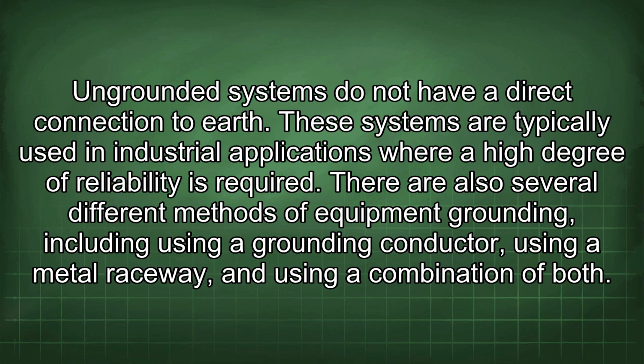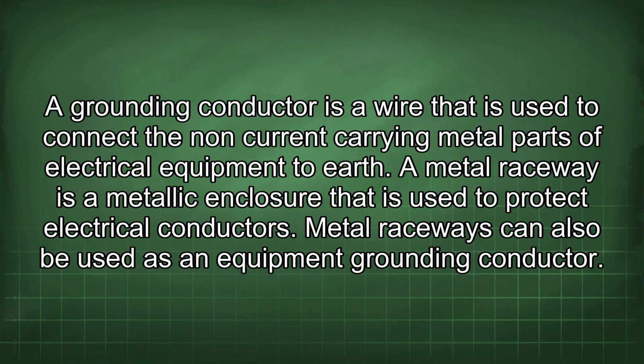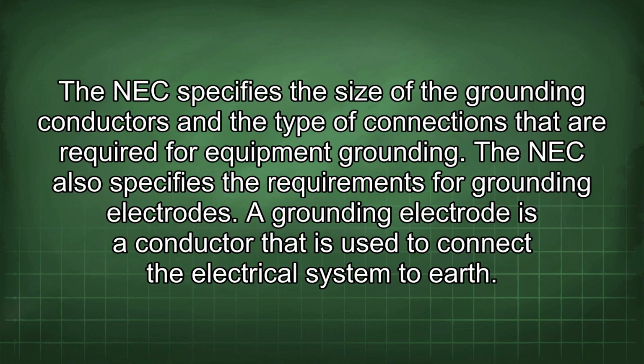There are also several different methods of equipment grounding, including using a grounding conductor, using a metal raceway, and using a combination of both. A grounding conductor is a wire that is used to connect the non-current carrying metal parts of electrical equipment to earth. A metal raceway is a metallic enclosure that is used to protect electrical conductors. Metal raceways can also be used as an equipment grounding conductor. The NEC specifies the size of the grounding conductors and the type of connections that are required for equipment grounding. The NEC also specifies the requirements for grounding electrodes.